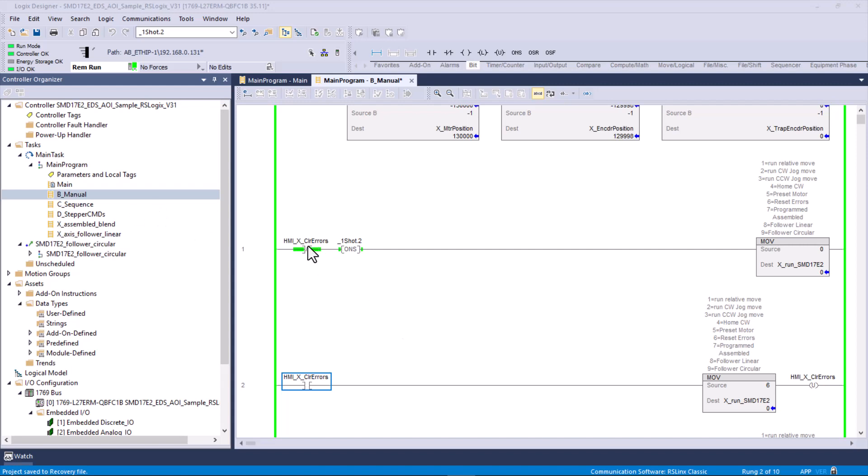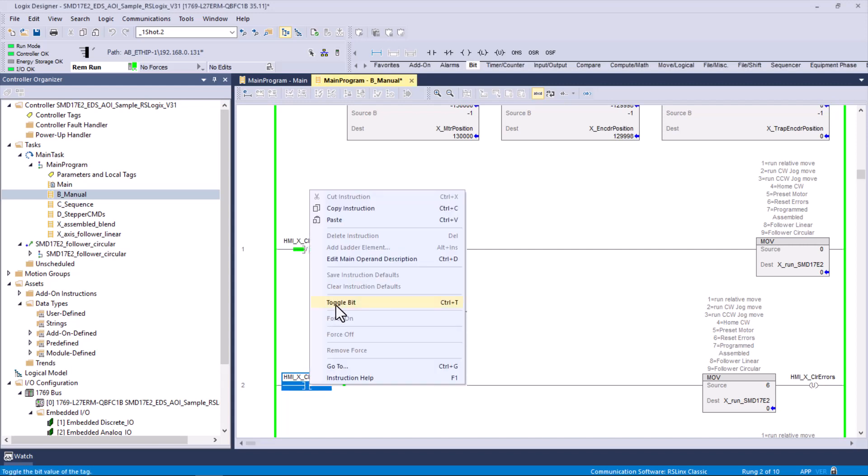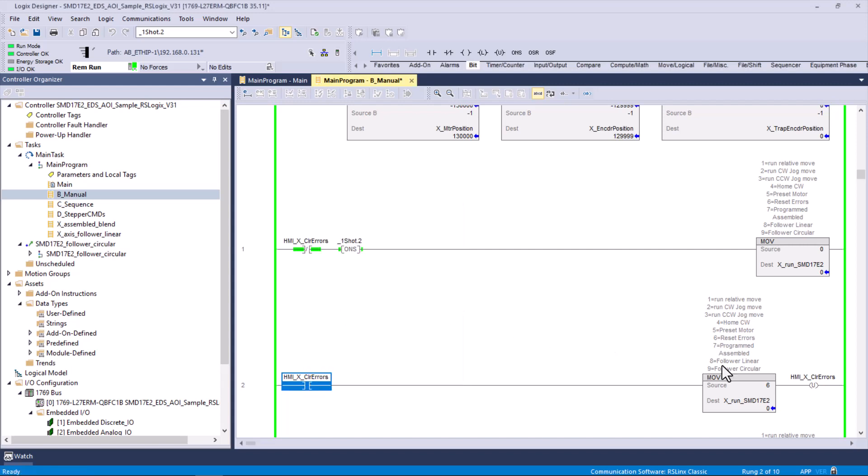If I want to do an immediate stop, I just push that button or toggle that bit. Now you see there's 11 in there and it's self extinguishing. However, we do like to leave a zero behind after we've completed any kind of a function. This rung puts a zero back in there when this bit goes off. So I right click, toggle bit, that puts a 6 in there. It unlatches this bit, and the next scan around it one shots a zero in there.